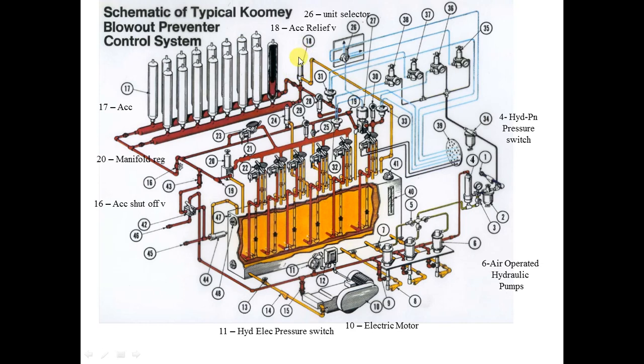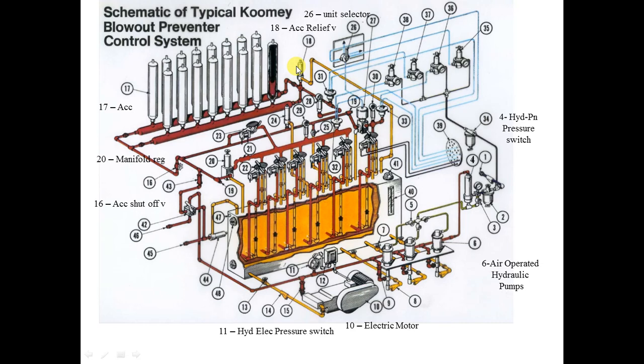Number eighteen is the accumulator relief valve — the second protection for the system. It is set at plus or minus 10 percent over the accumulator working pressure, which means 3300 psi. At this value the relief valve opens to protect all the system components from any failure in the power supply.